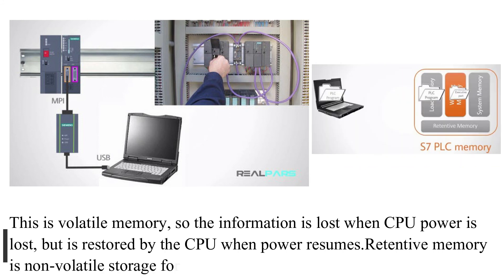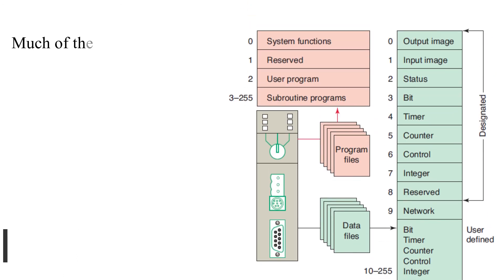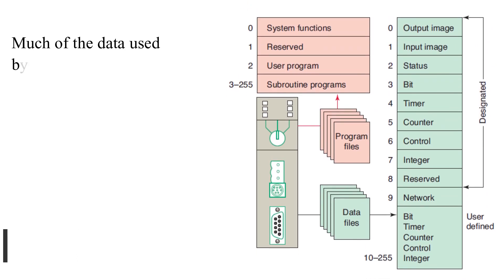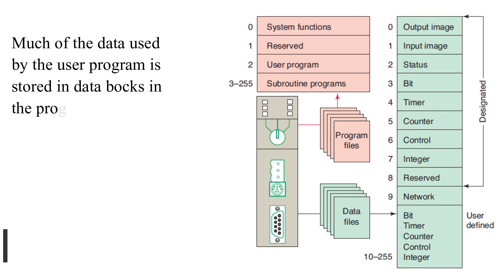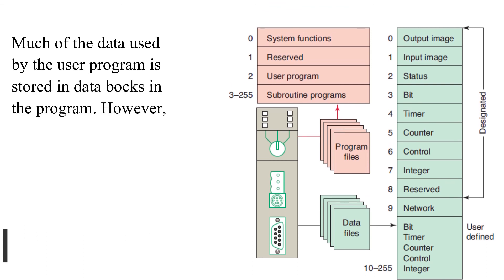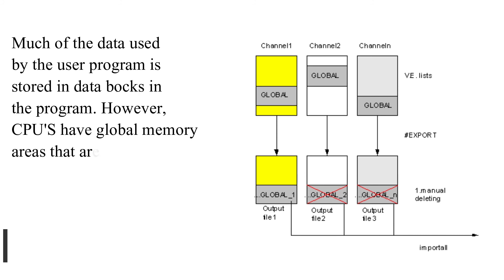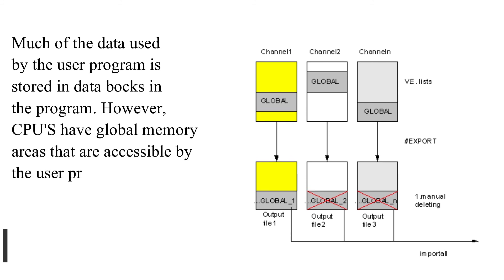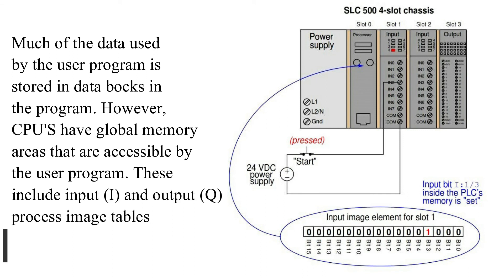Retentive memory is non-volatile storage for a limited amount of work memory information. Much of the data used by the user program is stored in data blocks in the program. However, CPUs have global memory areas that are accessible by the user program. These include input (I) and output (Q) process image tables and bit memory (M).